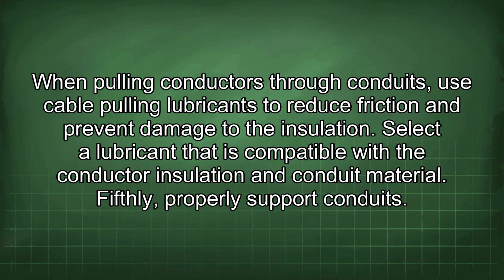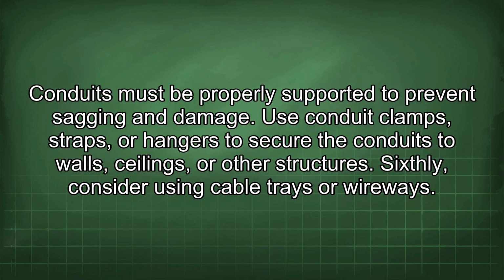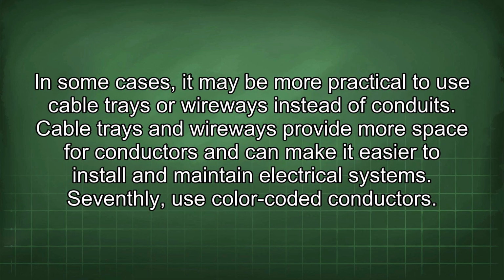Fifthly, properly support conduits. Conduits must be properly supported to prevent sagging and damage. Use conduit clamps, straps, or hangers to secure the conduits to walls, ceilings, or other structures. Sixthly, consider using cable trays or wireways. In some cases, it may be more practical to use cable trays or wireways instead of conduits. Cable trays and wireways provide more space for conductors and can make it easier to install and maintain electrical systems.